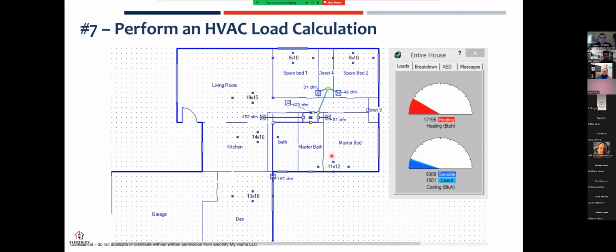But when we did this load calculation, we were very surprised. And the only thing the customer had done to the house before we looked at it was they had put really good windows in, really good low E, double pane, half inch gap vinyl windows, high quality. And then we came in, insulated the attic, and we were able to take a 36,000 BTU air conditioner and 60,000 BTU furnace out of this house.